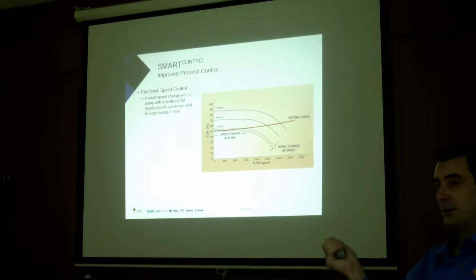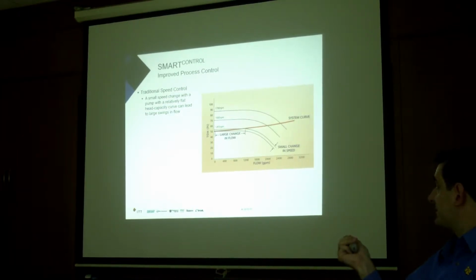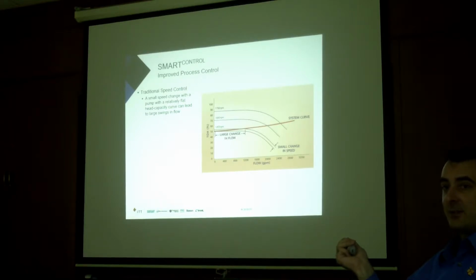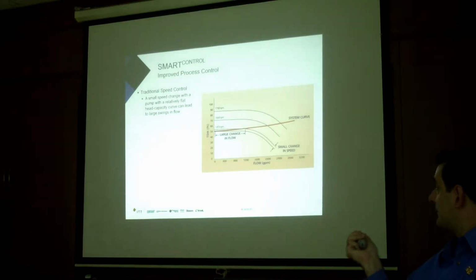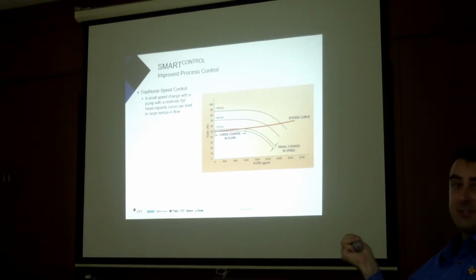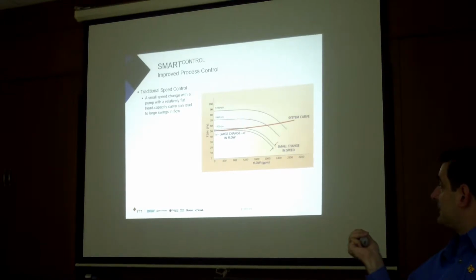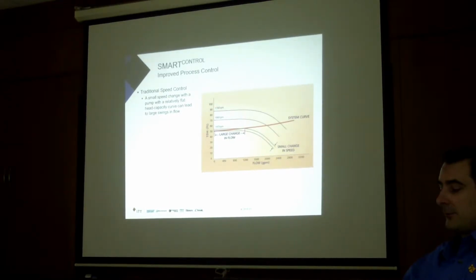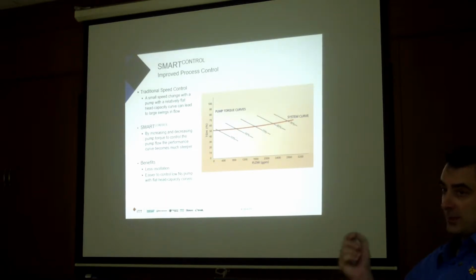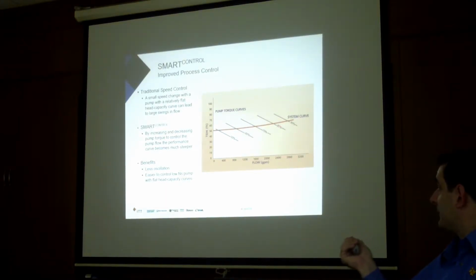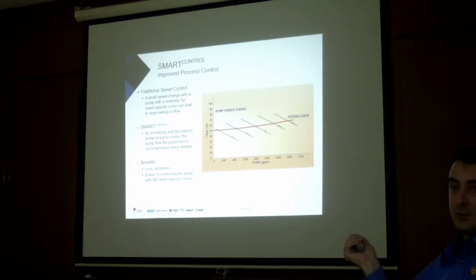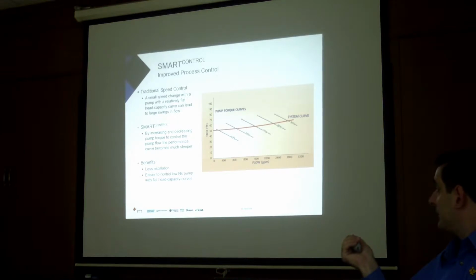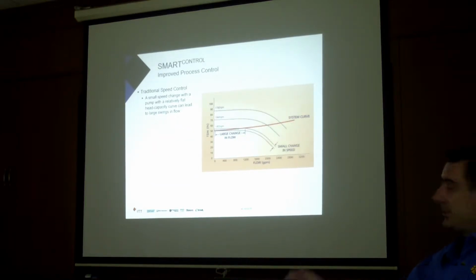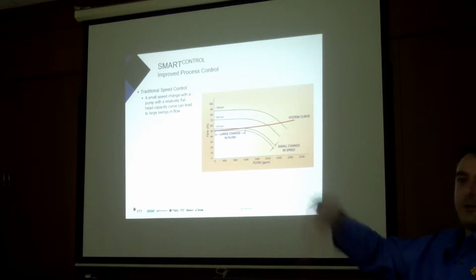This slide is very important in a way, especially for pressure control, because it shows here that whilst regular variable speed drives will change speed, the problem is that when the flat system curve meets a flat pump curve, a very tiny change in speed can have a very big change in flow. So you could do a tiny change in speed and all of a sudden be at zero flow. With the Pump Smart, we're using torque, so the same curve has a very strong gradient of torque that's easier for us to control. We can give you here, here, here very easily. Whereas on this one, you'll be swinging all over the place.